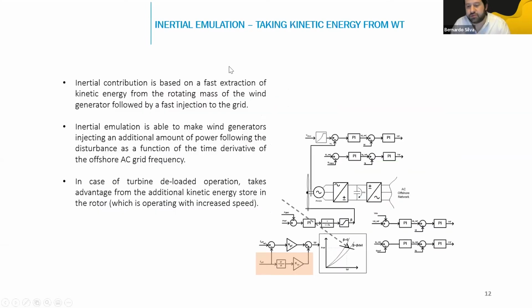We also wanted to try another thing: inertia emulation. We wanted to check if it was fast enough to capture the inertia emulation, which was set based on the derivative of frequency. We are able to quickly extract kinetic energy from the wind generator relying on the derivative of frequency and inject this as active power to the grid. The idea was to check first if we could do that, second if we could inject it, and third if it was effectively channeled towards the affected area.